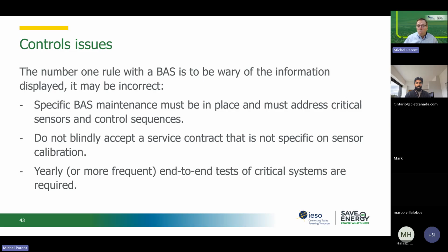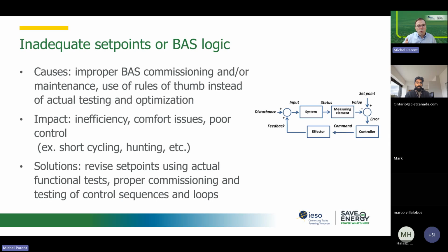Now, the one thing you have to be very careful about: they will sometimes say, we're going to calibrate all the sensors once a year. That is usually not done because there are too many sensors. Make sure that if you do have a PM program for your BAS, you have what's called a critical sensor list. What are the most critical sensors in my building? The ones that have the most influence on my energy use and on the reliability of my system. Make sure that those sensors are part of your service agreement, and that they are verified very rigorously once or twice a year, depending on your contract, by your service provider.